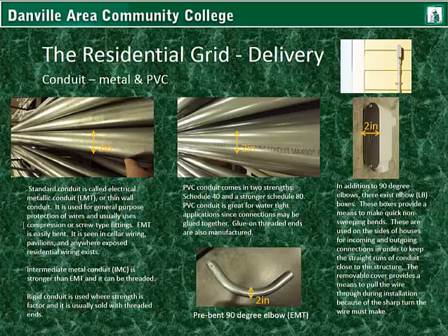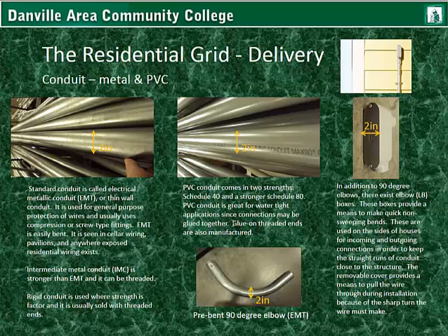Intermediate metal conduit, or IMC, is stronger than EMT and it can be threaded — basically it has a thicker wall. Rigid conduit is used for strength as a factor, and it's usually sold with threaded ends. Getting away from the metal conduit, there's also PVC conduit, and it comes in two strengths: Schedule 40 and the stronger Schedule 80. PVC conduit is great for watertight applications since connections may be glued together. It is also easier to assemble, and glue-on threaded ends are also manufactured for PVC.